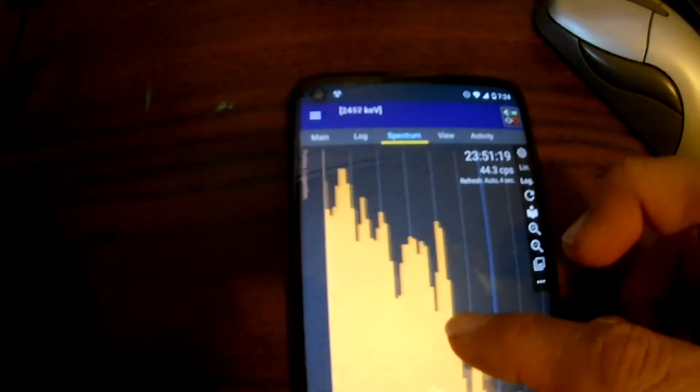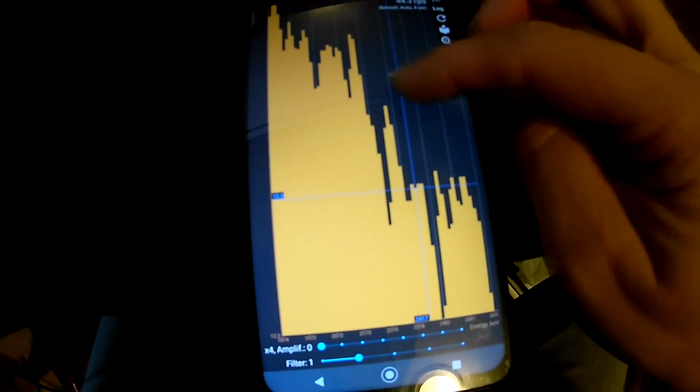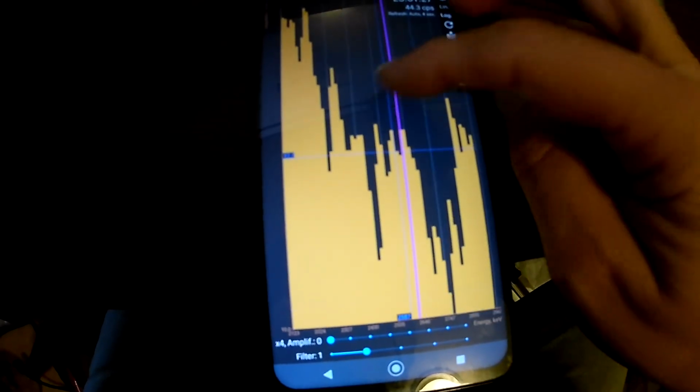So these purple lines tell you where these peaks should be for these different isotopes. Okay. And again, the calibration might be a little bit off, so it might have to be recalibrated, because they're just doing a linear interpolation. Okay, so a peak there would be for thorium.